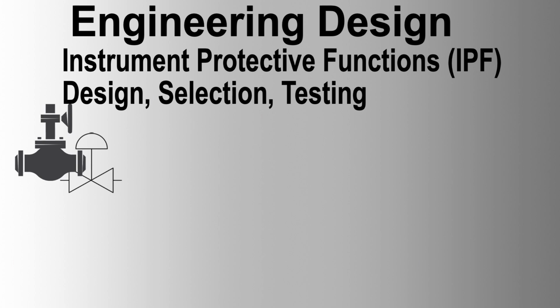Digital inputs. The IPS should provide the wetting voltage for digital inputs which are connected to switches with voltage-free contacts, e.g. reset and emergency shutdown switches. For solid-state sensors, e.g. proximity sensors, voltage-carrying inputs should be provided. Normally open digital inputs should be provided with open and short circuit detection per input channel. The detection results should be available for use in the application logic. Normally open digital inputs for field-mounted reset switches, MOS enable switches, lamp test, acknowledge, and reset switches in local panels do not require open and short circuit detection.